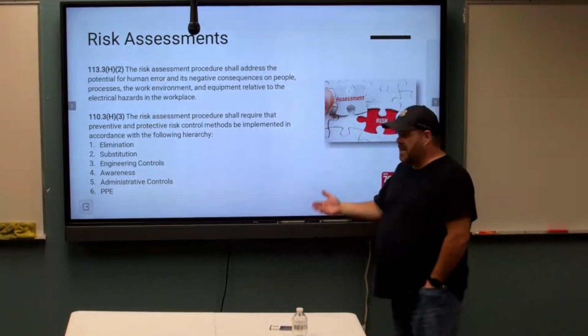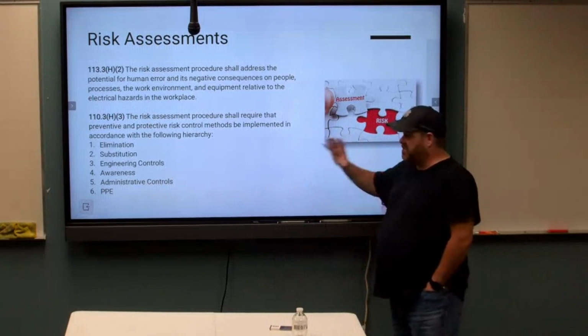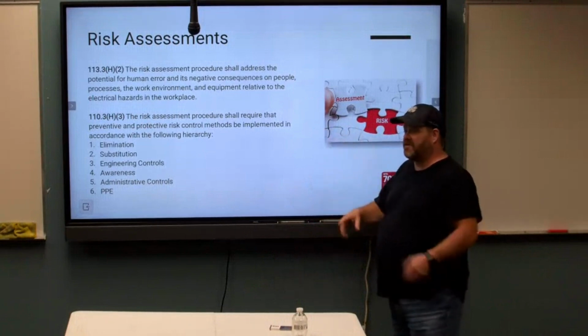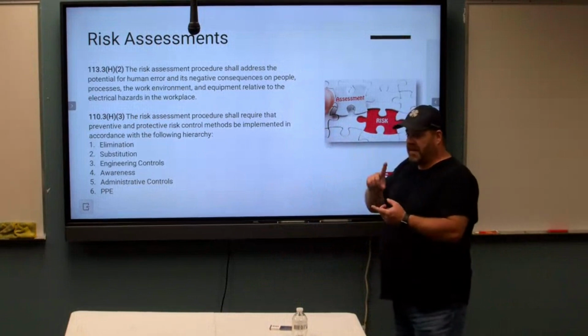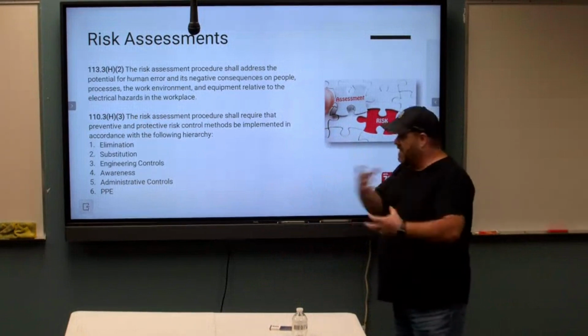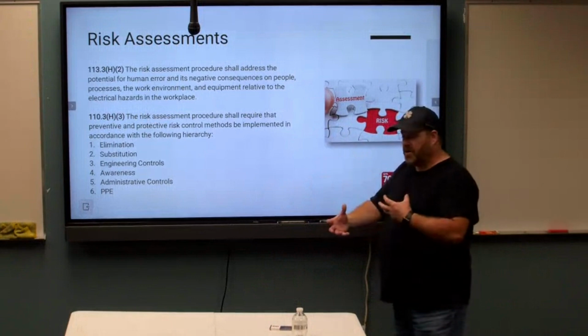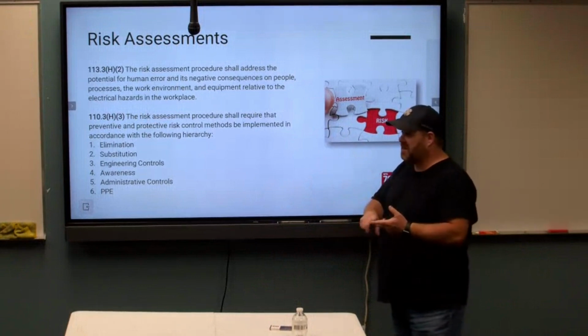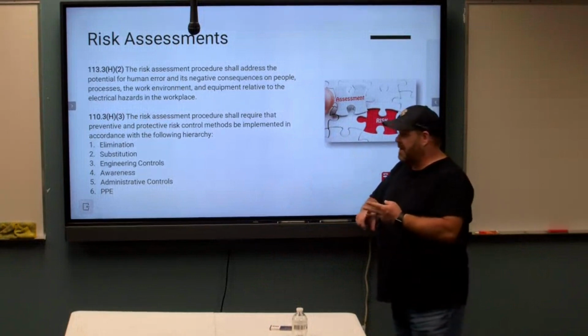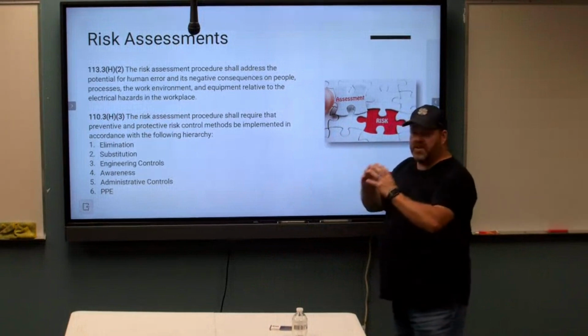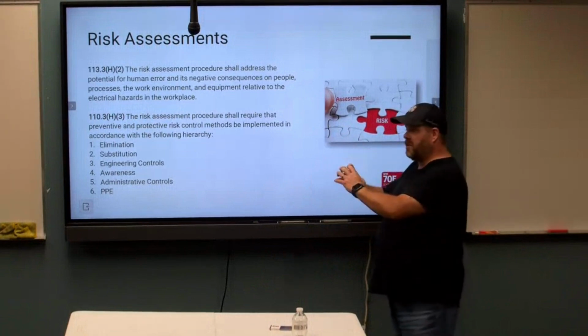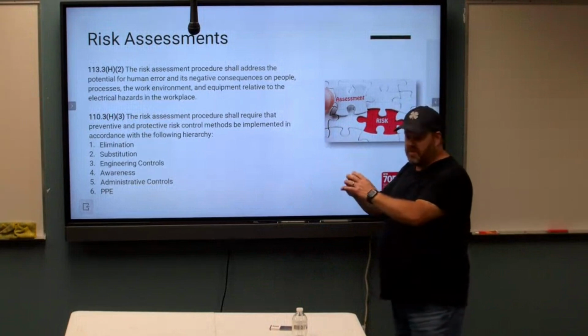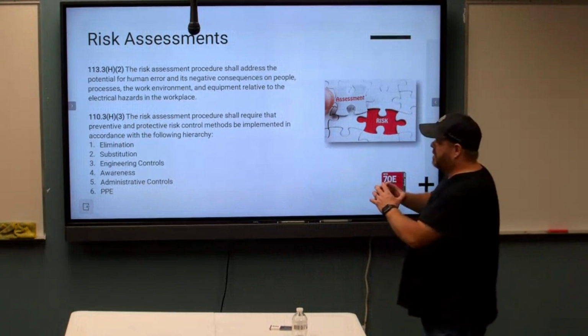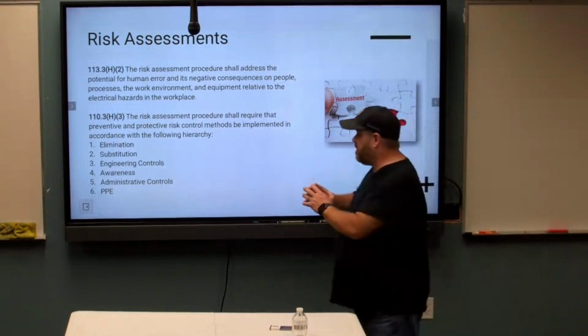But in 2018, they made a major change and said, okay, this is what we want to see on a risk assessment. We have to look at the potentials, like what the hazard is, how bad the outcome's going to be. Is it going to be a first, second, or third degree burn? Put all the controls in place and reevaluate to see what the outcome could be after all our controls are in place.